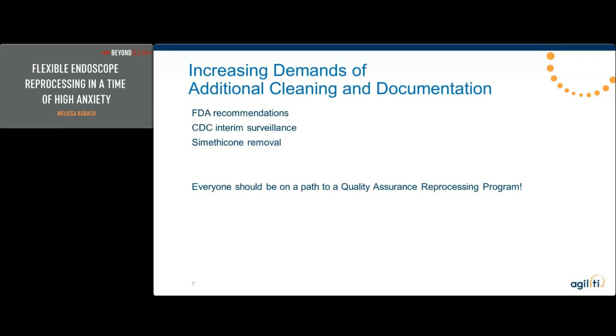Many of the facilities are conducting ATP test swabs specific to the elevator area, and the FDA has acknowledged that detection of adenosine triphosphate may be an effective method for measuring reprocessing effectiveness. All manufacturers are transitioning to disposable aspects for duodenoscopes, and additionally, water-insoluble substances such as simethicone have been minimized, but it's still injected through the working channel via lavage at the majority of the facilities I visit.